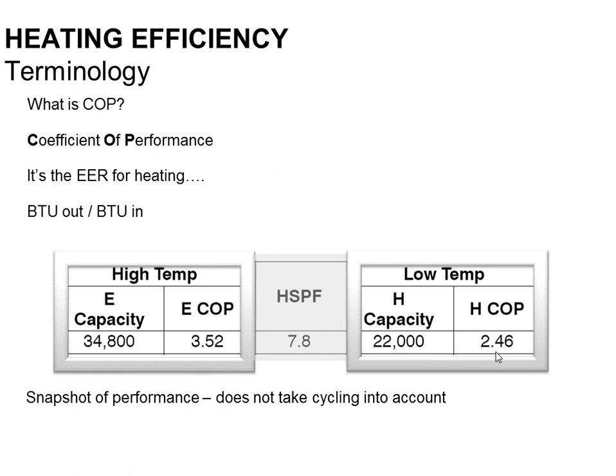COP, coefficient of performance, is just a ratio of how much power did I buy versus how much capacity did I get. So if I have a COP of 1.0, that basically means for every kilowatt hour I buy from the power company, I get 1 kilowatt hour of heating capacity. So it's a 1-to-1 relationship. So a 1.0 COP means it's 100% efficient, right? So if I had the best furnace money could buy, which I believe these days is a 98% efficient furnace, the COP would be 0.98, right?